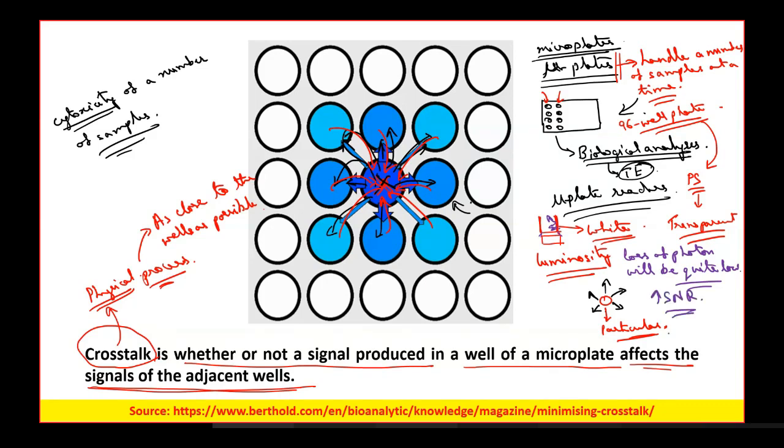Usually, the normal microplates are transparent. But in the case of a luminometer, you can coat the borders of the wells white, so that first of all the radiation cannot go out of the way and you can collect the information only from the bottom of the wells.